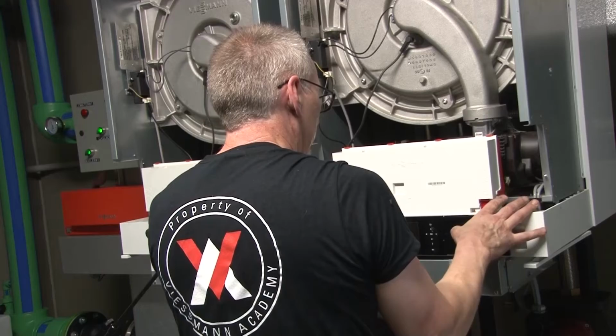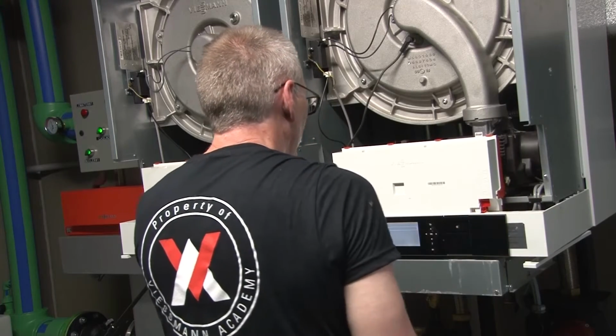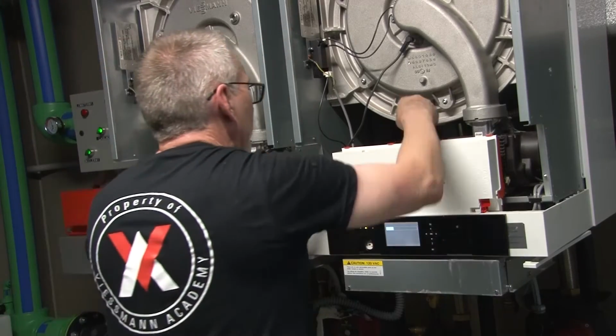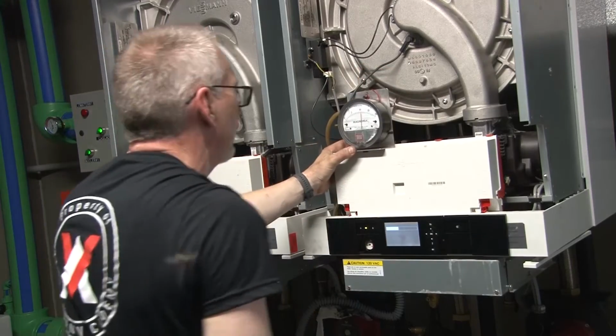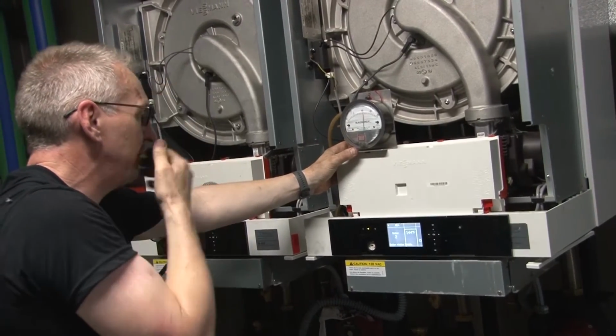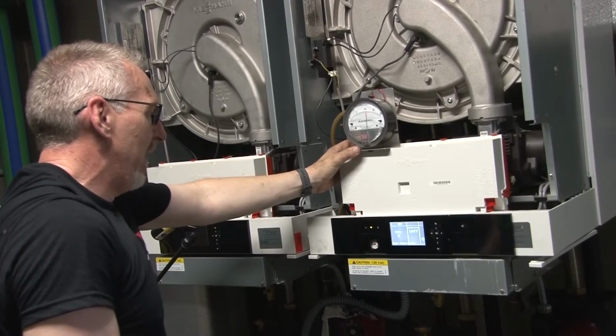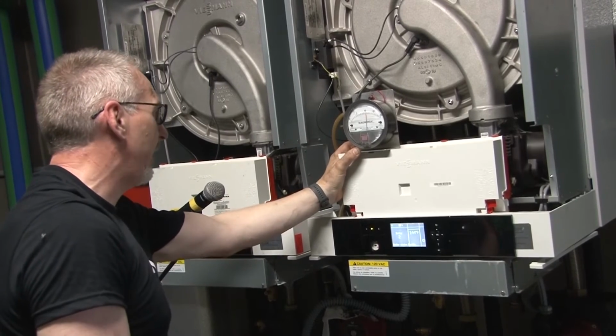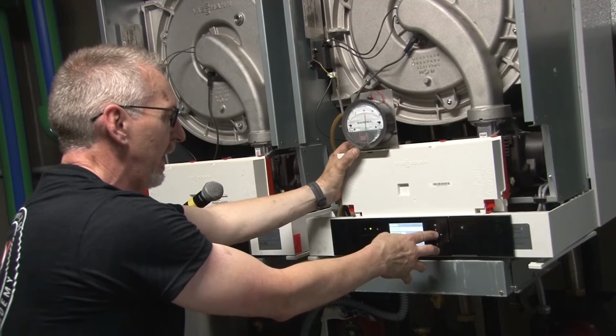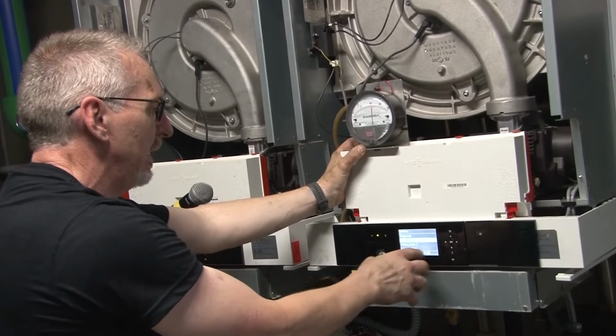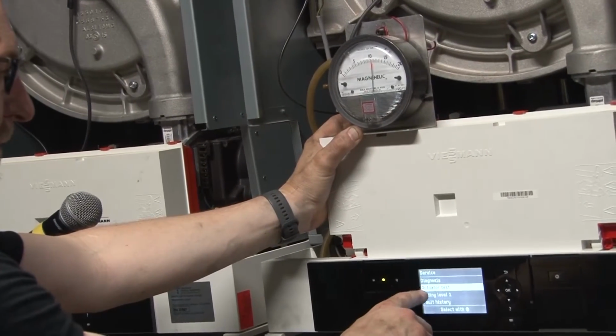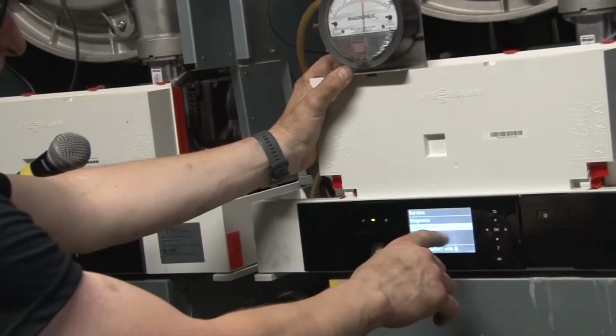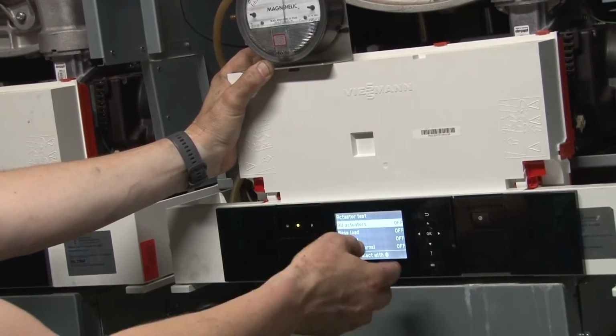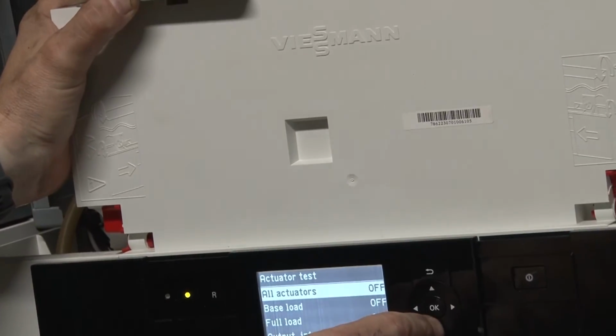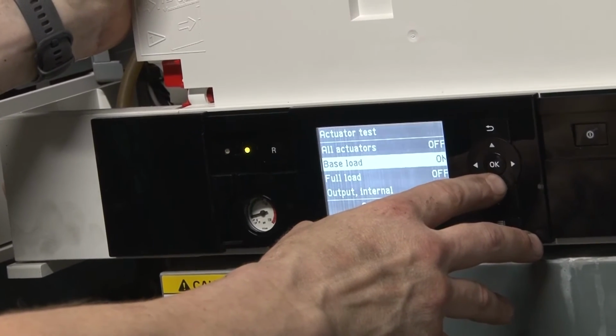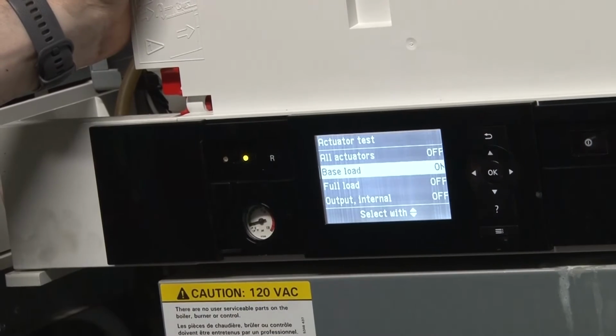And I'm going to make a test here. I've got the gauge still on. We'll pop it up here. You can see that we're at 11 inches of pressure here. And if I want to control the burner, I want to put it into high fire. I can get myself into service. And I just don't want the burner to fire here. I want to control it. So if I go into service and I see diagnosis, that's a great area for service information, temperatures and set points, etc. Actuator test is where I'm going into. And I'm now controlling everything. I can turn pumps on manually. I can control mixing valves. I have mixing valves on the boiler. But when I turn the boiler on and it fires, base load is low fire.